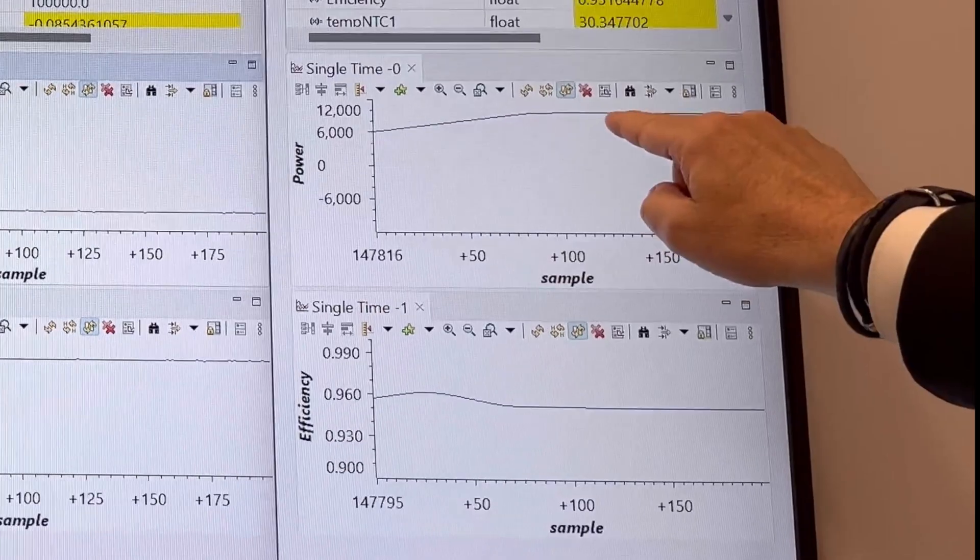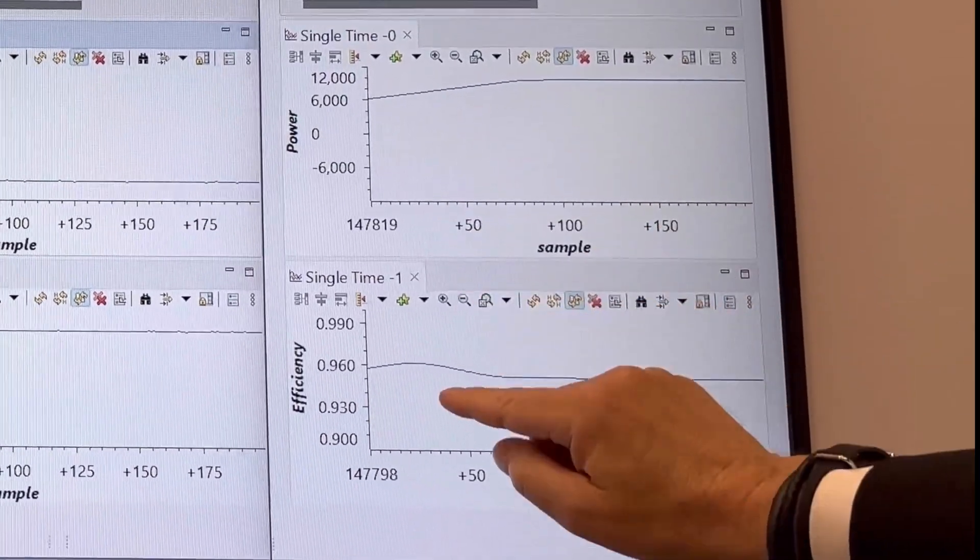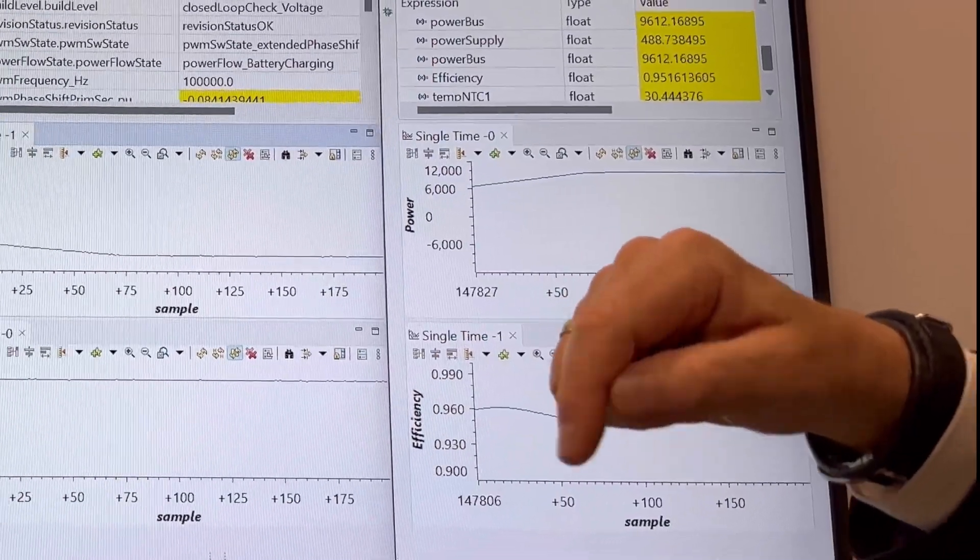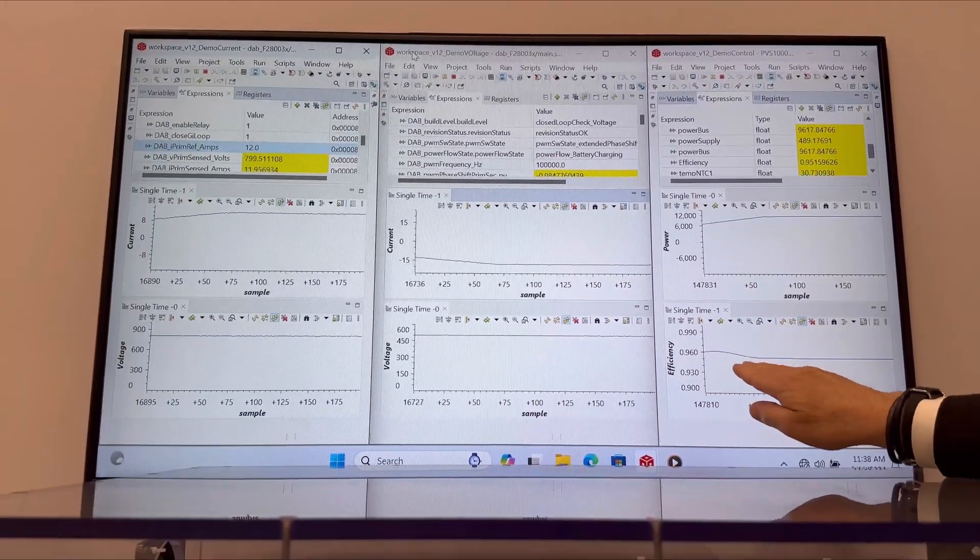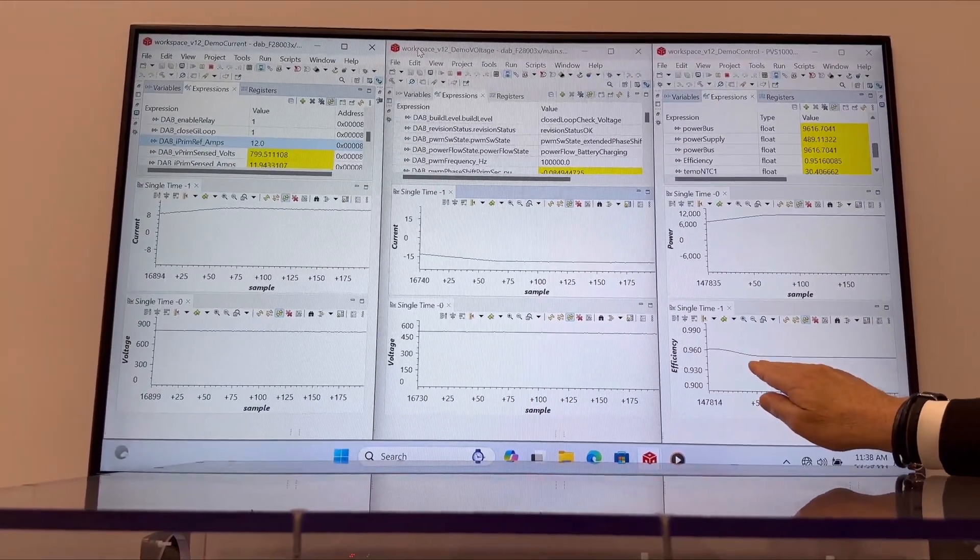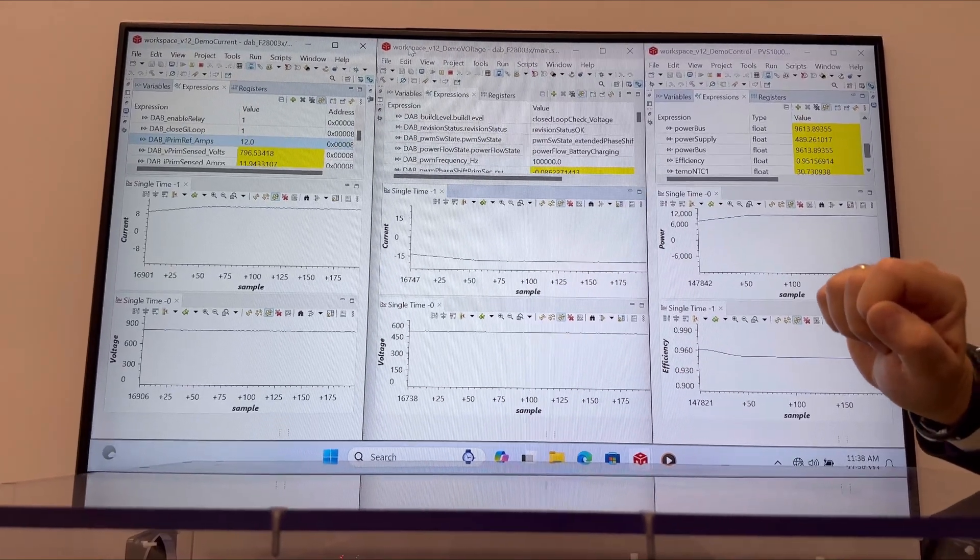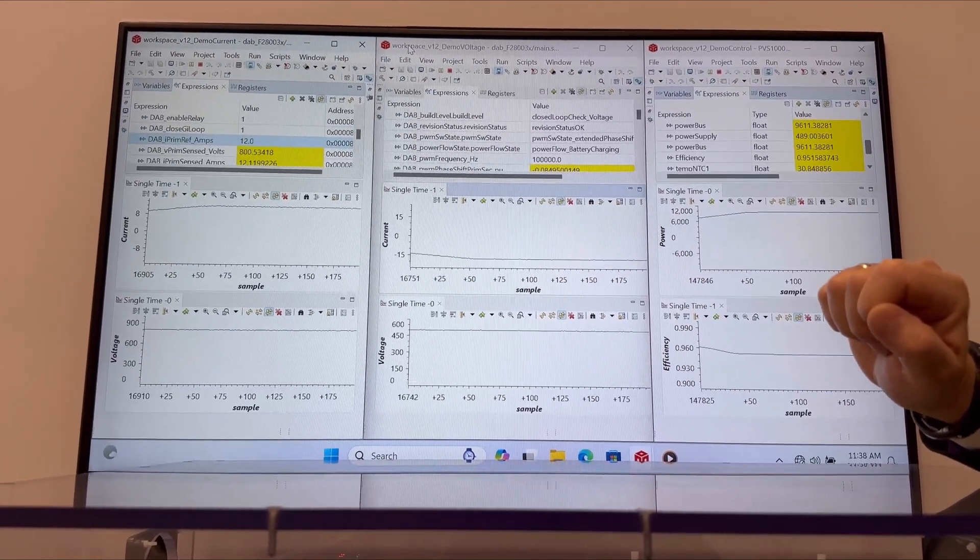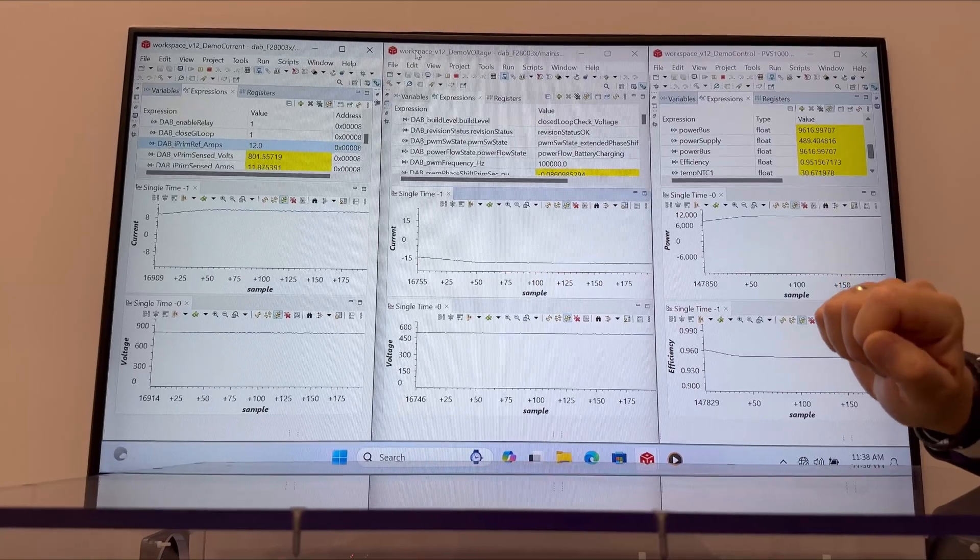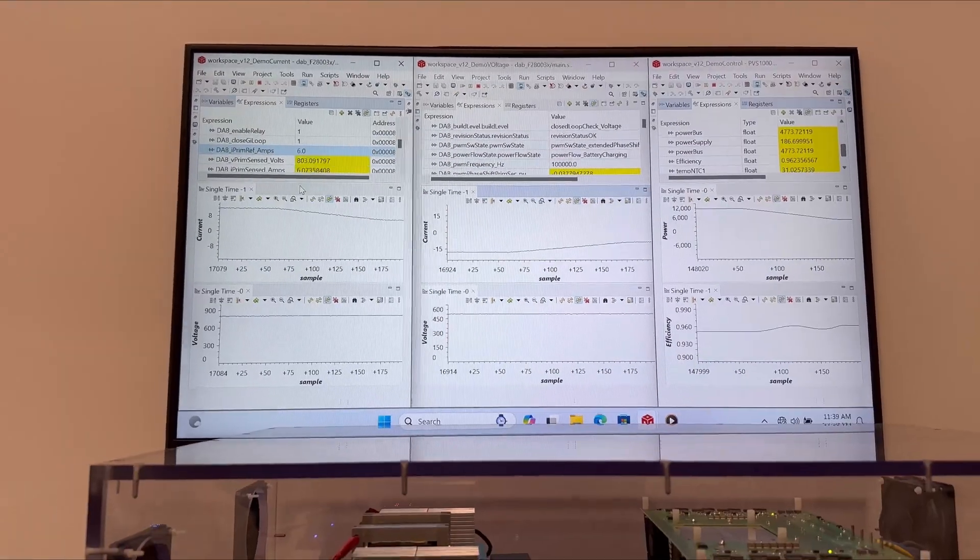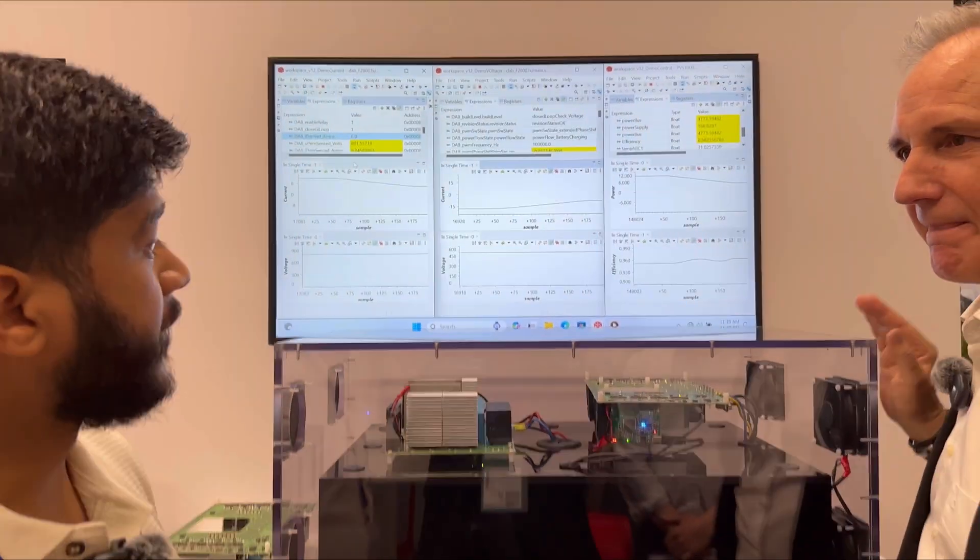Here you see actually the efficiency for both converters. It's combined, 96 percent for both converters. So each one is running at 98 percent efficiency, which is very, very high for such a high load actually.